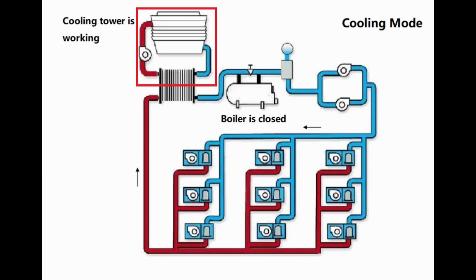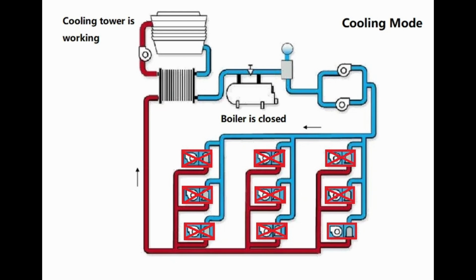Here are some things to keep in mind during the installation of new controls on the central plant. The water loop needs to be pumped around the building constantly in case any of the heat pump units get a call for heating or cooling. If the flow of water stops while the unit is running, it is possible for a high pressure or low pressure condition to occur and trigger a mechanical safety. Some of these safeties will reset on their own once the pressure has normalized, but some will need to be reset manually, requiring a technician to go to every unit on the loop. So it's important to keep the pumps running as you are installing new controls on the central plant.